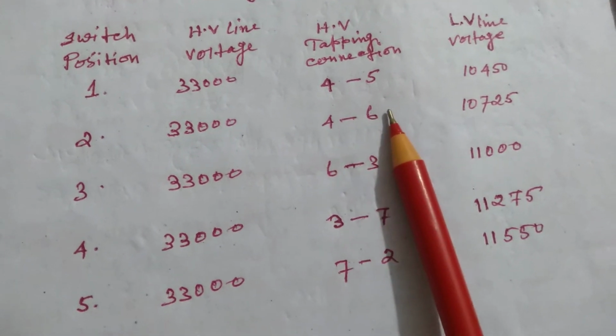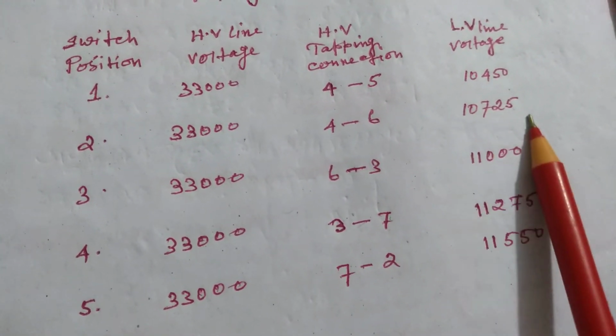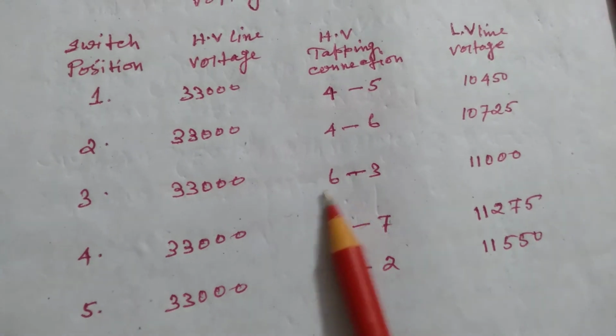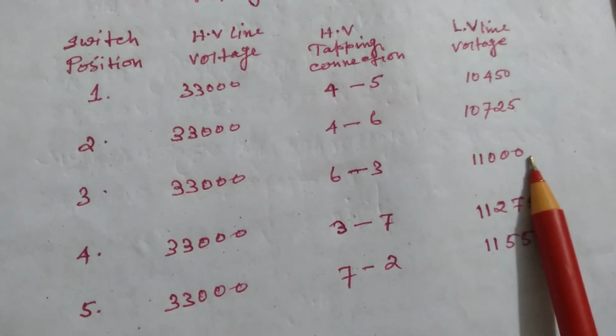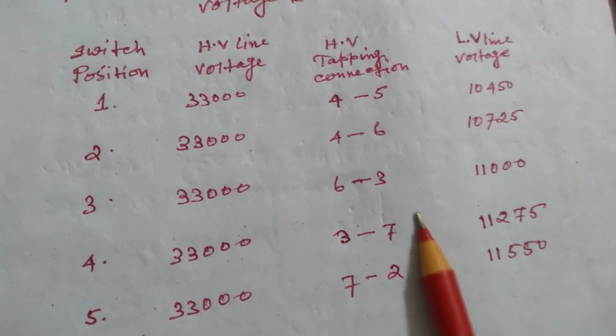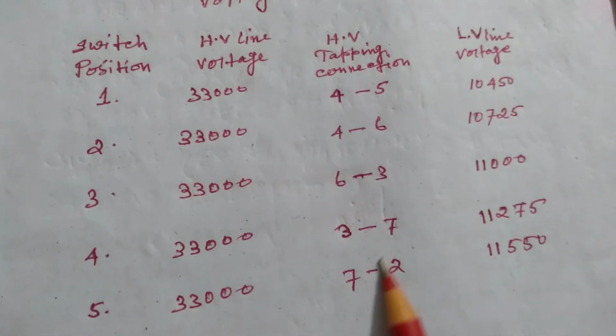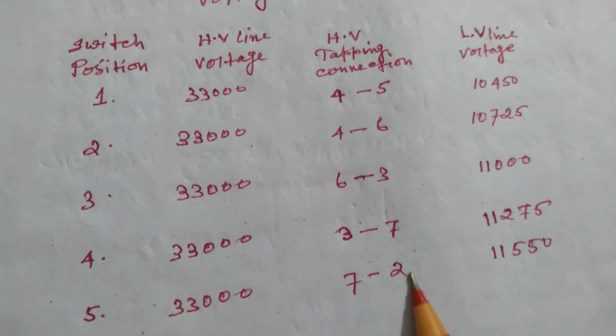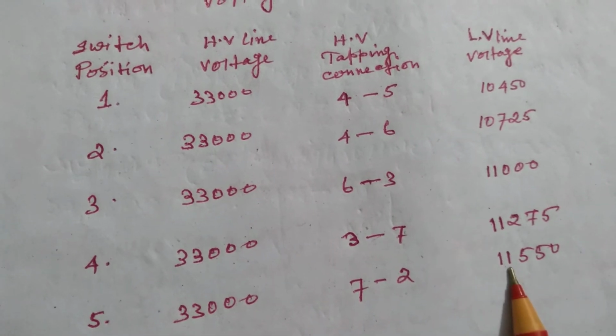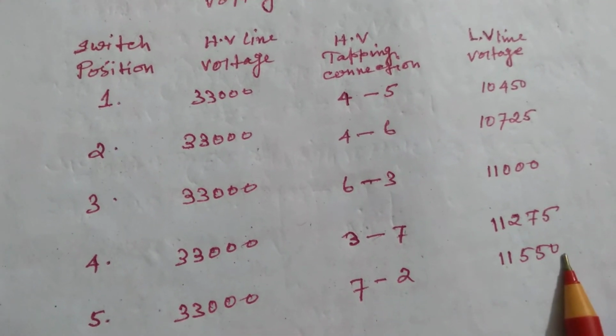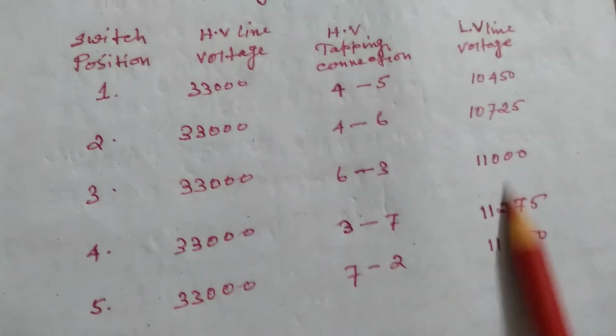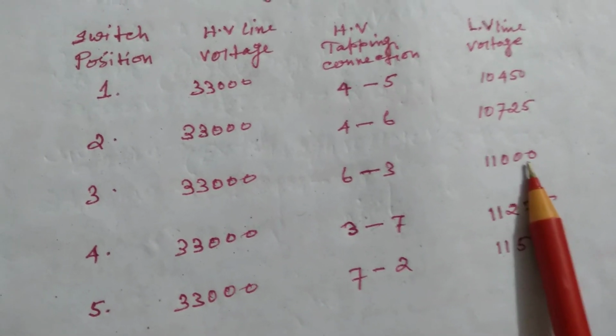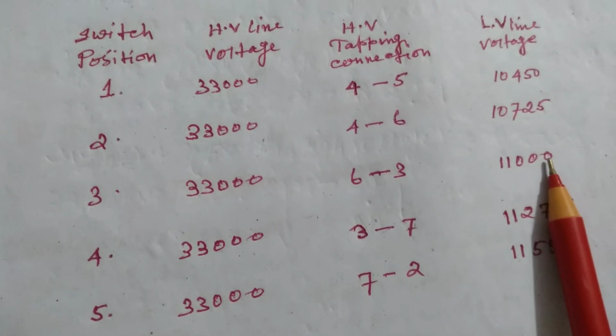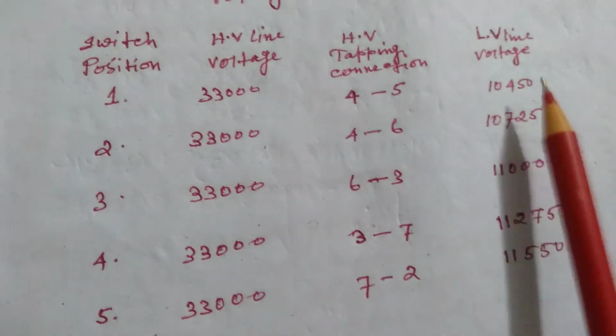4 to 6 tap changing 10,725, and 6 to 3 11,000, 3 to 7 11,275, and 7 to 2 tap changing 11,550 if required, but standard is 11,000 volt, 11 kV.